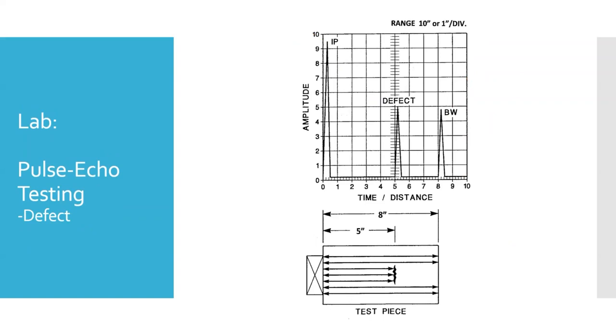This defect reduces the back wall peak amplitude because we don't have as big of an area bouncing the sound back at 8 inches now. The other thing you can see is that even though they only show 3 of the sound waves bouncing to the crack, that one's higher because now that sound isn't traveling as far. But the big key is you can see how far that crack is from the front face of the part.